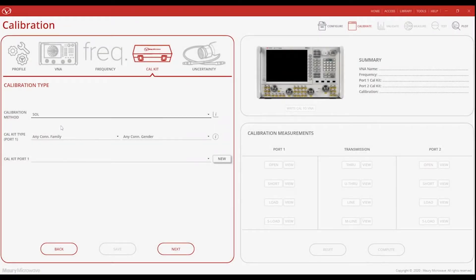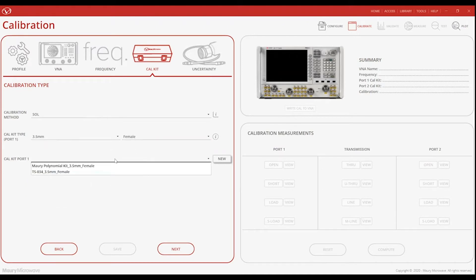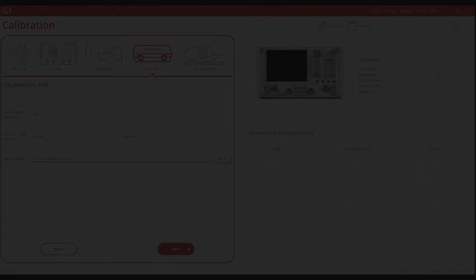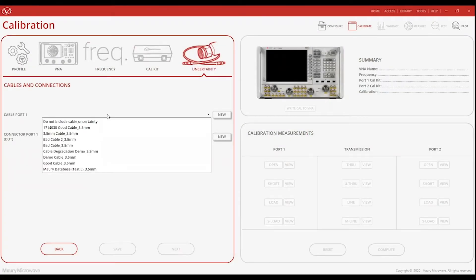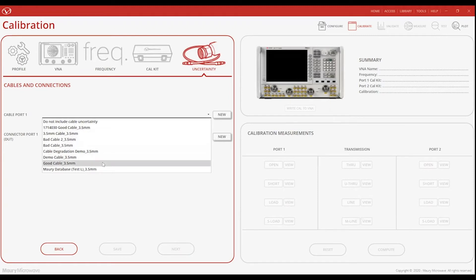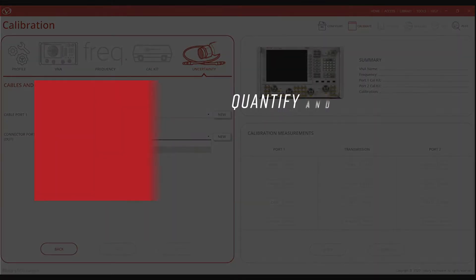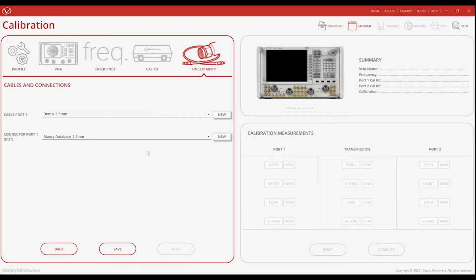Following that step, we will define our calibration method, connector type and gender, and specific calibration kit being used from our database. And finally, we can define cable and connector uncertainty so that they are included in our calibration and DUT measurements. I'm going to include the characterized uncertainty of the specific cable assembly being used today, since I mentioned earlier uncertainty will be critical in our calibration validation process. For more information about characterizing uncertainty, please watch our Insight uncertainty demonstration on YouTube. Now, back to the demo.